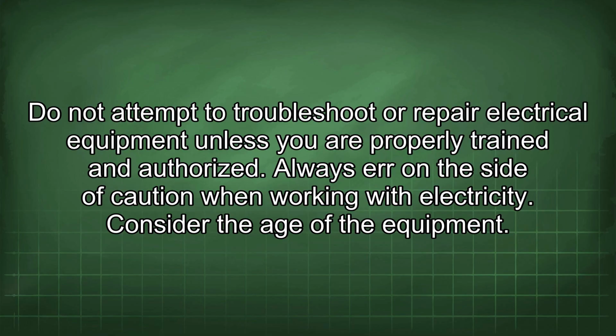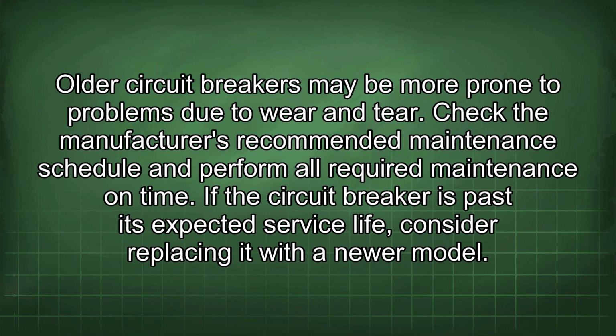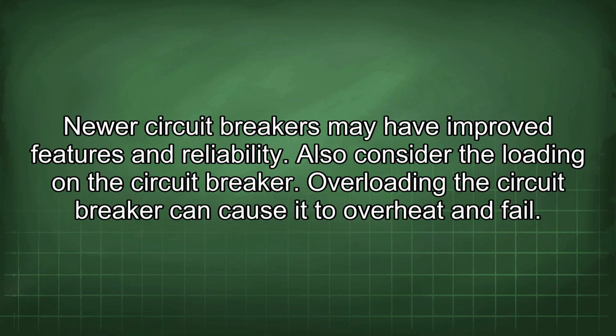Consider the age of the equipment. Older circuit breakers may be more prone to problems due to wear and tear. Check the manufacturer's recommended maintenance schedule and perform all required maintenance on time. If the circuit breaker is past its expected service life, consider replacing it with a newer model. Newer circuit breakers may have improved features and reliability.